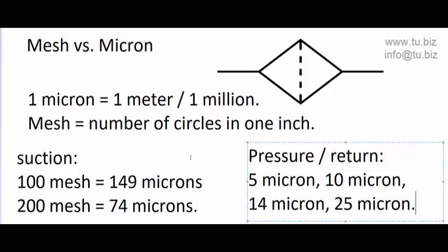Now, if we want to reach the levels of filtration of the ISO 4406 target, we're going to have to use fine filtration. If you have servo valves or proportional valves, we're going to have to use very fine filtration, given a 5 micron filter. For a pressure filter, we can still put a 10 micron, but likely it's not going to protect a servo valve. Let's say I will put a 3 micron in the pressure line. But that's how we usually do the filtration.